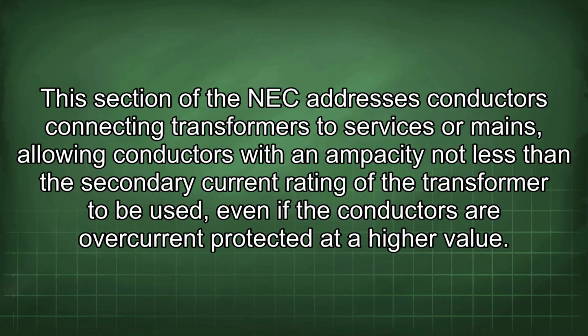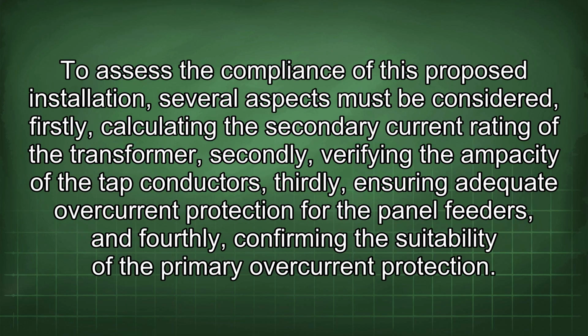240.21(C)(3). This section of the NEC addresses conductors connecting transformers to services or mains, allowing conductors with an ampacity not less than the secondary current rating of the transformer to be used, even if the conductors are overcurrent protected at a higher value. To assess the compliance of this proposed installation, several aspects must be considered.